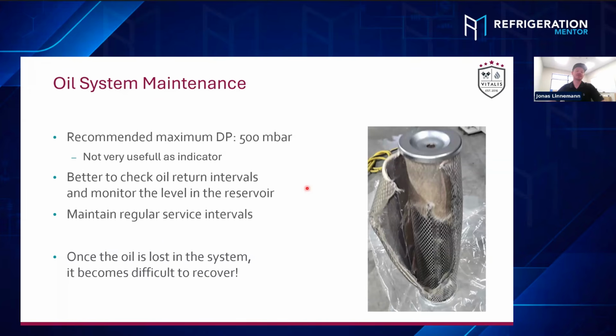And if you just listen to the oil return valve and you can't hear anything, that's the best indicator that this cartridge needs to be replaced. Also, sometimes just closing the oil return line and waiting until the sensor detects oil, but then it's not able to drain it, right? So then you have a longer window to see that it's really separating. But that's pretty much the best indicator of the quality of oil separation and the cartridge itself.